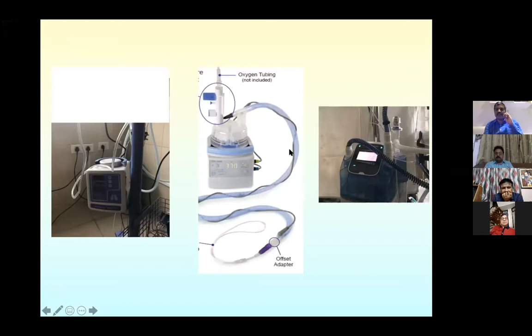Then comes the next part, which is the air, oxygen, blender. Air gives 21% oxygen. Oxygen gives 100% oxygen. To give how much of the fraction oxygen we have to give to the baby, we have to have a blender, because this blender mixes the air and oxygen in such a way that the gas coming out of the blender has appropriate FiO2. Suppose you set FiO2 50%, then it will mix the air and oxygen in such a way that the air coming out from the blender has 50%.